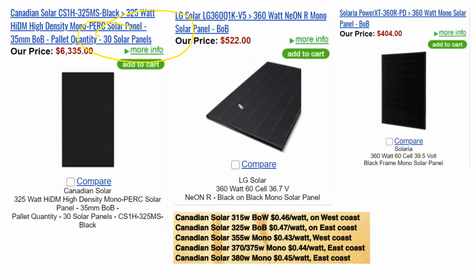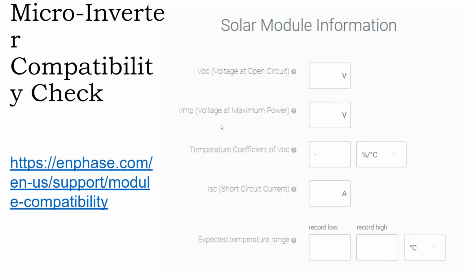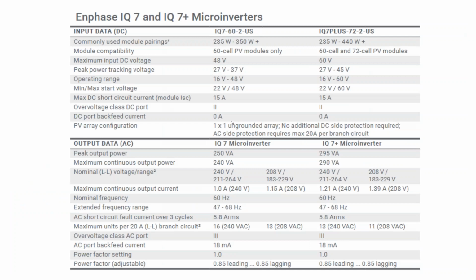If I have a roof surface where I can only fit 24 panels on my rooftop, then I might go buy a pallet based off the pallet quantity. If it has 25 panels per pallet versus 30 panels per pallet, sometimes that's the difference in nailing your project in terms of hitting your budget needs. So microinverters are very easy to design with. You can have up to 16 per 20 amp branch circuit for their residential product.